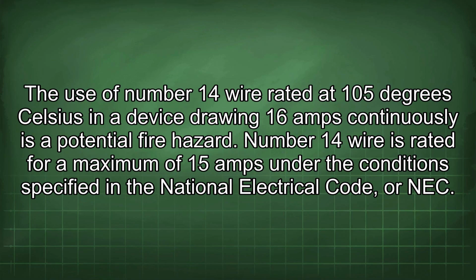The use of number 14 wire rated at 105 degrees Celsius in a device drawing 16 amps continuously is a potential fire hazard. Number 14 wire is rated for a maximum of 15 amps under the conditions specified in the National Electrical Code, or NEC.